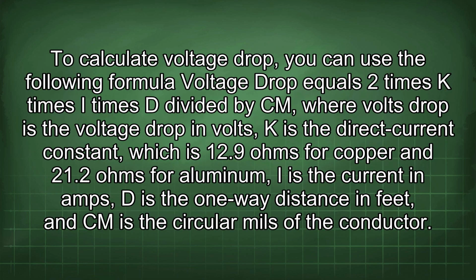To calculate voltage drop, you can use the following formula: voltage drop equals 2 times K times I times D divided by Cm, where the voltage drop is in volts, K is the direct current constant, which is 12.9 ohms for copper and 21.2 ohms for aluminum, I is the current in amps, D is the one-way distance in feet, and Cm is the circular mils of the conductor.